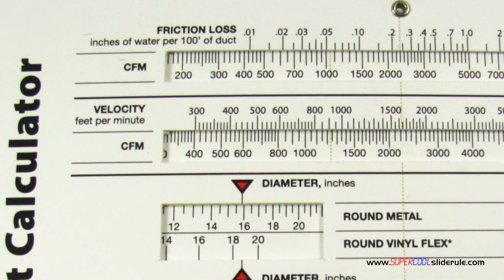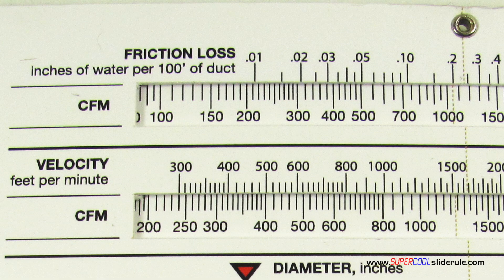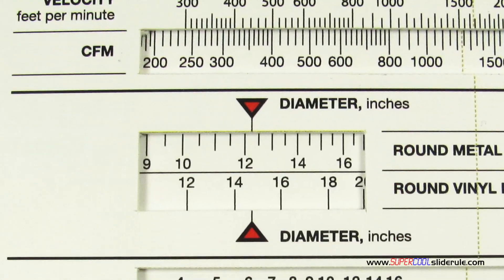And the required duct size will be 20 inch for a single return. If two returns are desired, then 500 can be indexed — 500 for each return duct — and the size would be two 16s or a 14 and a 16.